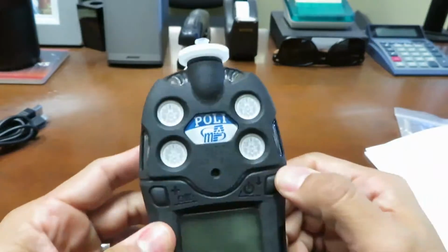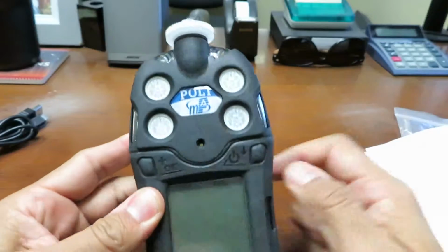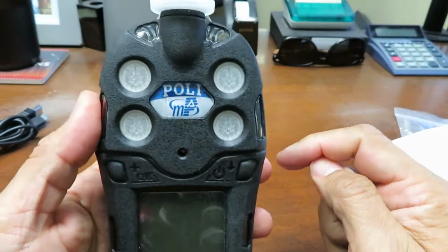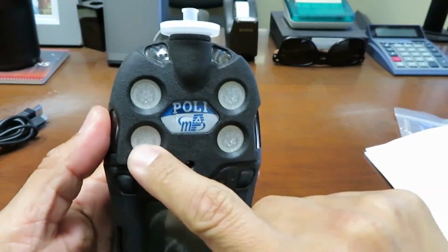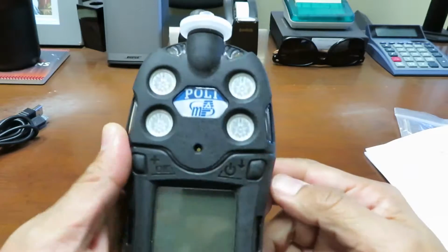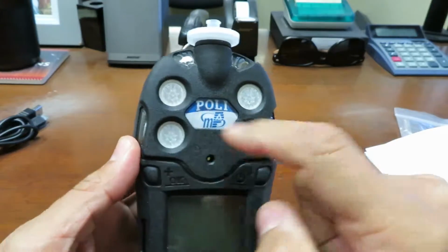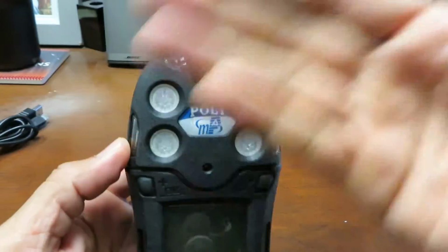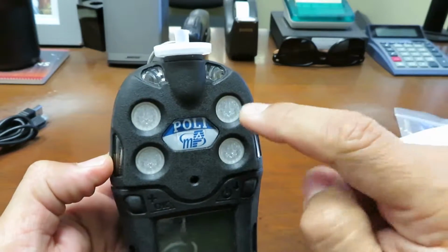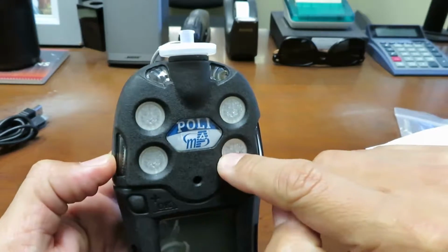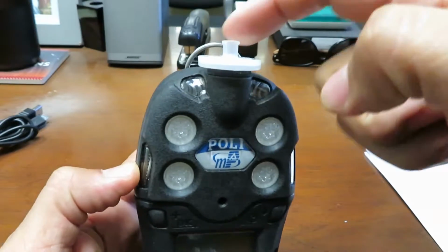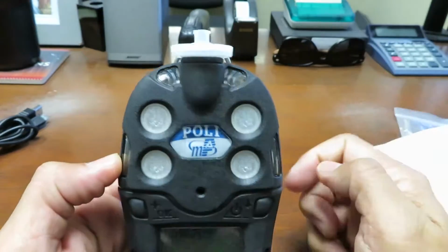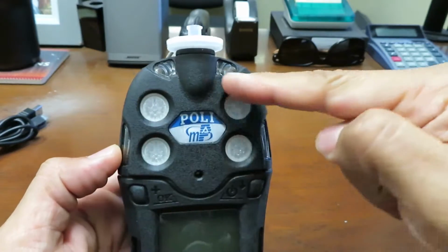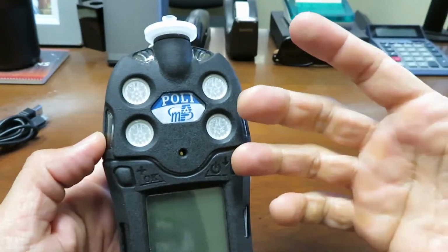Now here's something different. As I mentioned, this is a pumped unit, but all of these are exposed, whereas in most units, if it looks like this, it means it's a diffusion unit, which requires ambient air to blow across the sensors. However, this is the exhaust for all the sensors — air comes in through here and actually exhausts out over the sensors. The good thing about this design is you need no calibration cup.